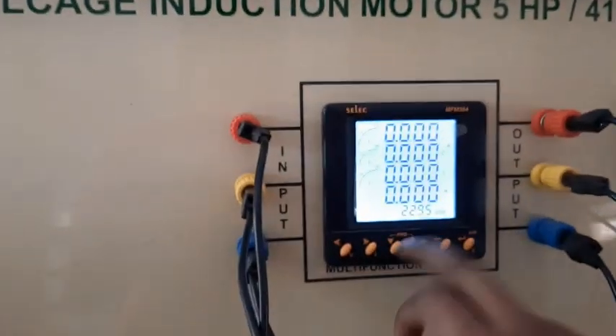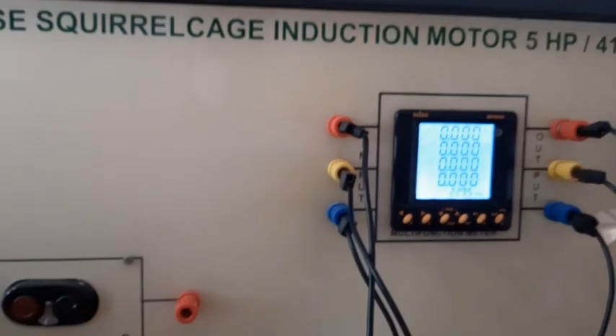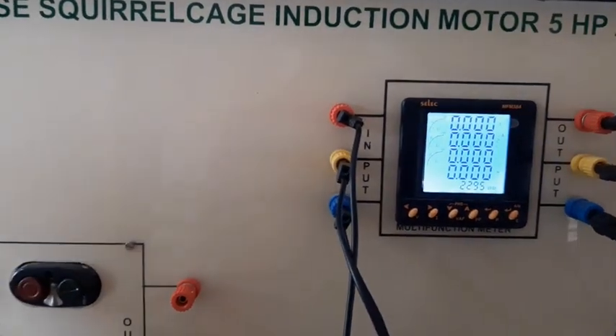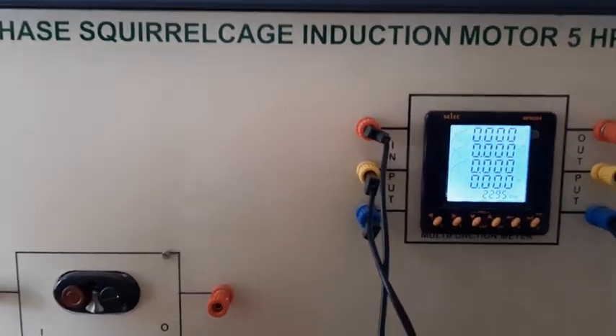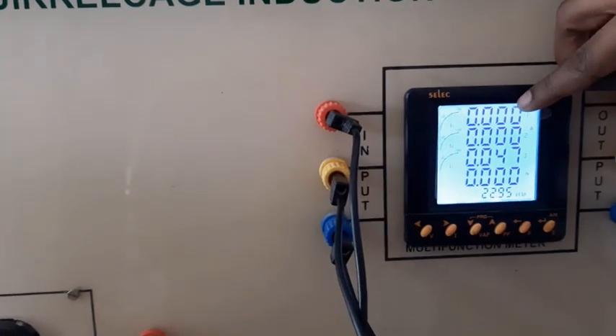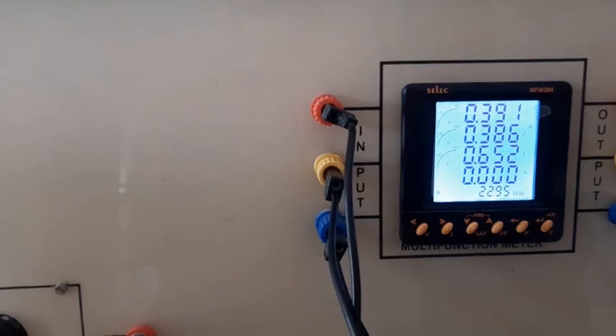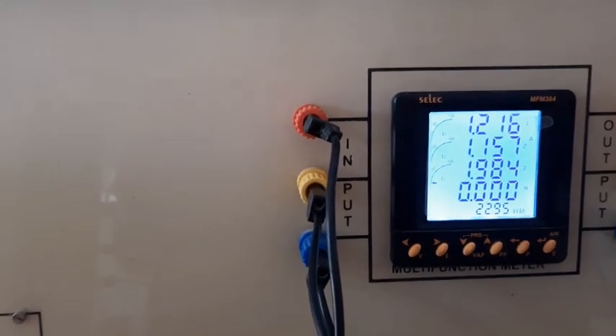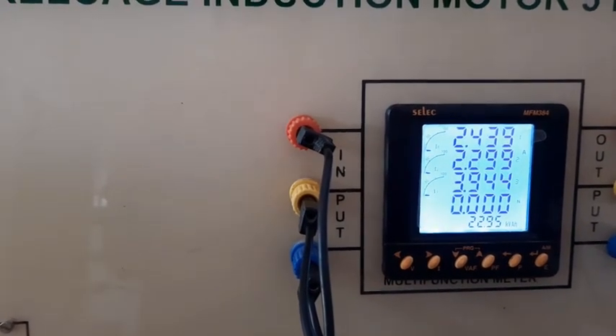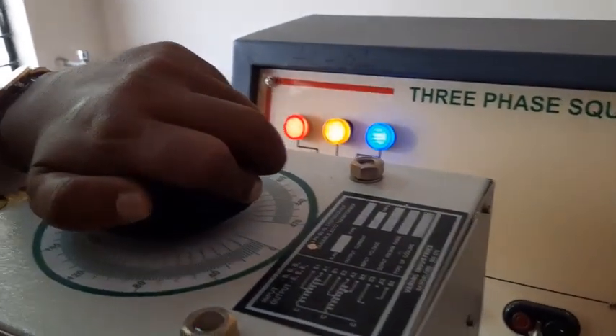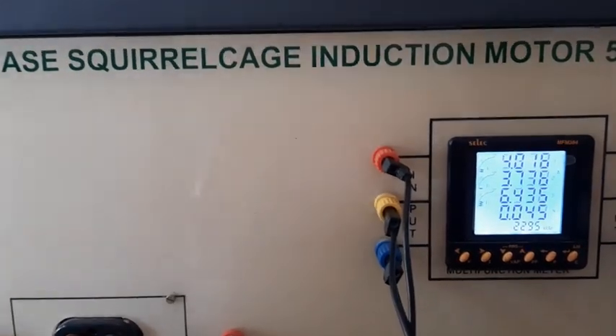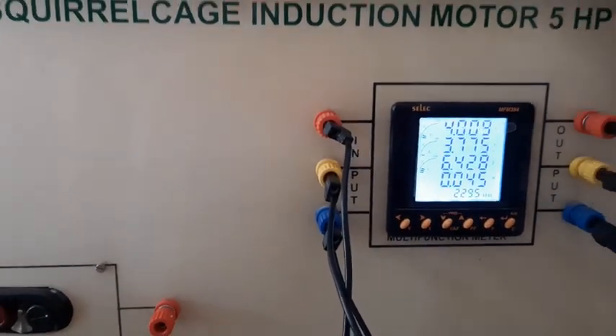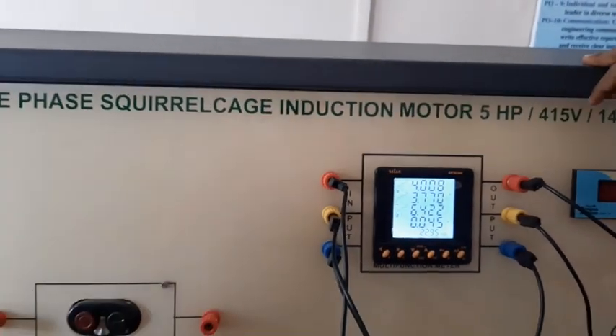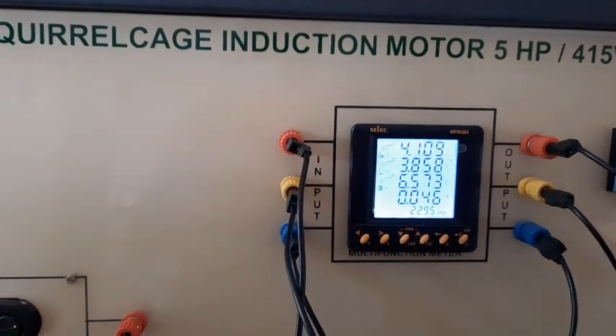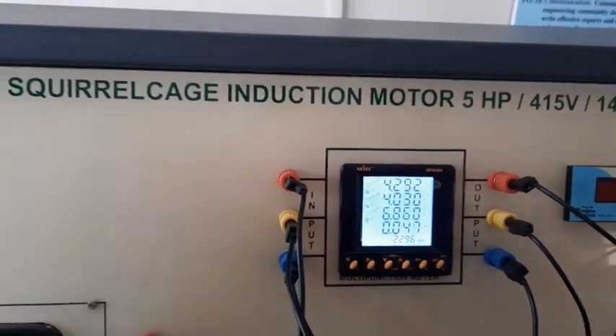Initially keep the meter on the current reading, not the voltage reading. That is the current reading in terms of ampere. Now switch on the supply. Slowly, don't apply 415 volt now. Slowly apply voltage. The current is slowly rising to 4 ampere, slowly increase, slowly, 4.2, 4.3. Okay, this is enough.